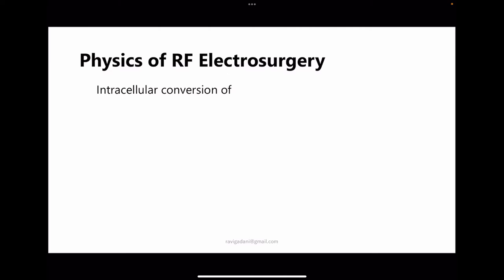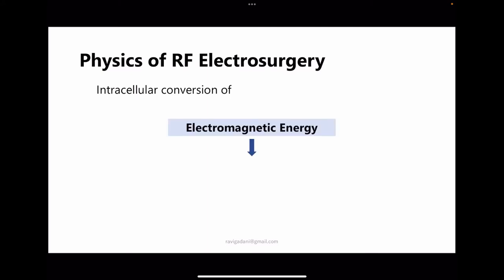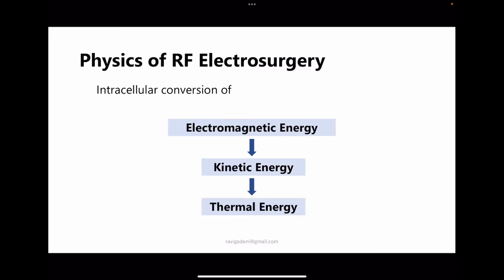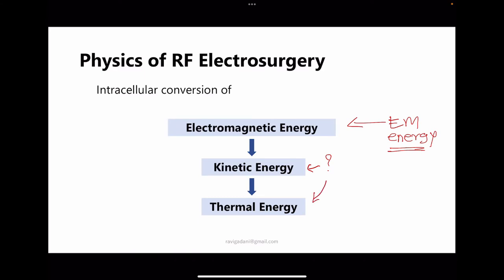The fundamental principle of how electrosurgery works is intracellular conversion of electromagnetic energy to kinetic energy to thermal energy. What we provide is electromagnetic energy, and we will see how it is converted into kinetic and then thermal energy.